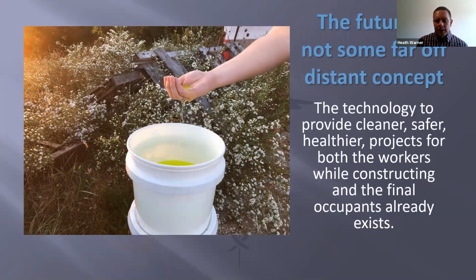So as we talked about a lot of the new equipment that's available out there. The model, the yellow liquid that you see in that pail and what the model is holding in your hand, that's the glycol that runs through the hydronic heating system. Most people, when you tell them glycol, they think antifreeze in your car. That's deadly if you let your dog lick it. Don't do it. It's sweet. It's actually a propylene glycol. That propylene glycol is so safe. It's USDA approved for direct food contact. It's one of the main ingredients in shampoo, hand sanitizers, and women's cosmetics. In fact, the higher end women's cosmetics that they charge you a fortune for, they actually have a higher amount of glycol in them, even though it's relatively inexpensive.